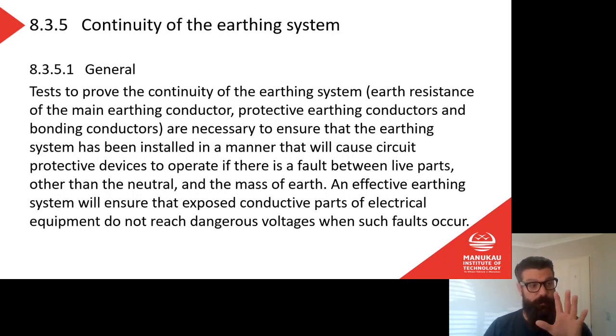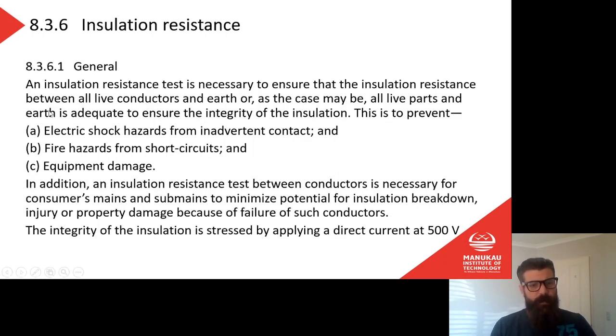If it didn't blow the circuit breaker, then when I touch that thing that the phase conductor is touching, I will get a shock. Okay, insulation resistance. An insulation resistance test is necessary to ensure the insulation resistance between all live conductors and earth, or, as the case may be, all live parts and earth, is adequate to ensure the integrity of the insulation. This is to prevent electric shock hazards from inadvertent contact and fire hazards from short circuits and equipment damage.